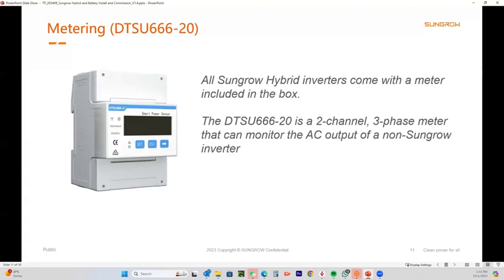Most of our range, in fact all of the hybrids, are supplied with a meter. The single phase ones, the 5 and the 6, will have an S100 meter, but all the other ones have the DTSU666-20, which is a 3-phase meter. It's a 2-channel meter, and what I mean by that is one set of CTs will sense the mains for your import-export control, and there's a second channel which can sense the output of a third-party inverter.